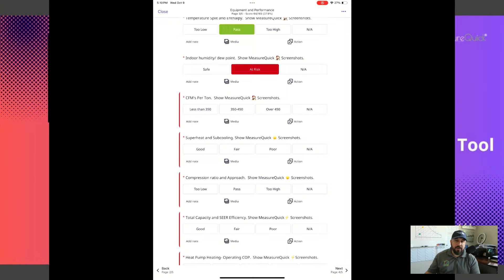This is where I also break out the true flow grid from the Energy Conservatory, because I want to quantify my airflow. MeasureQuick does a very good job quantifying airflow, but if the system is really messed up on the refrigerant side, sometimes those numbers are a little skewed. I want to know exactly what my airflow is, and that's what the true flow grid does for me.